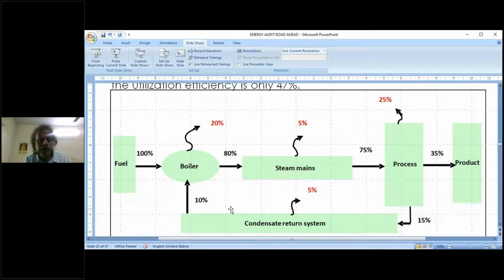Now, where do you focus on reduction? The boiler itself, as we have seen, technologies have emerged to an extent where the efficiency of the boiler is 80%. The 20% that remains, how much further we can reduce it becomes a challenge. For steam mains, insulation has already been done, there's a 5% loss. Further insulation may be too expensive, not economically viable. So 5% let it remain. Now 75% is going into the process. This is where a major portion of the energy saving lies. If you save maybe 1% here, at the input of the boiler you may be saving about 5%. And there is a lot of scope for saving energy in this process.